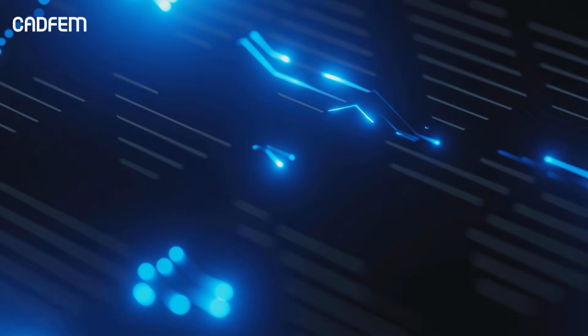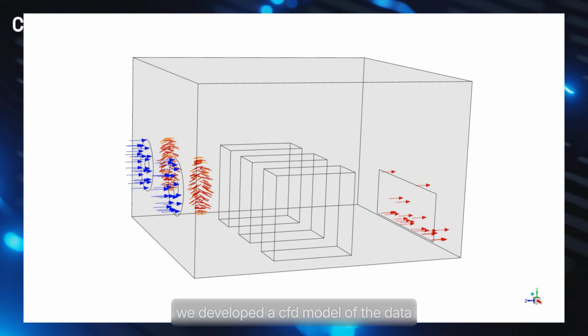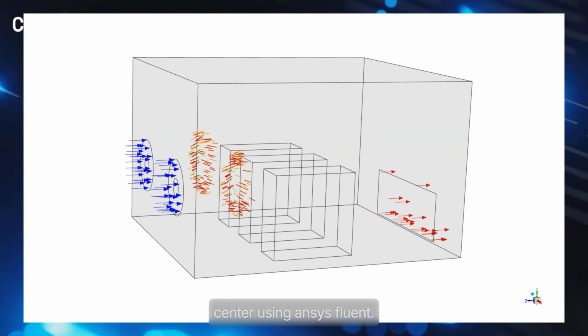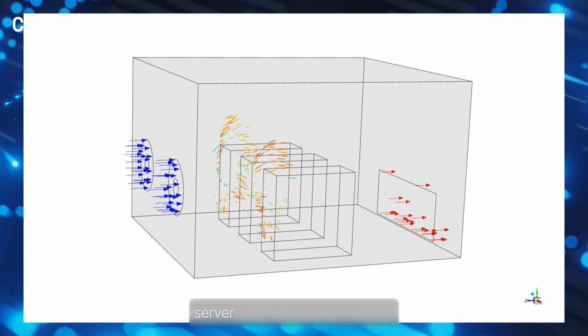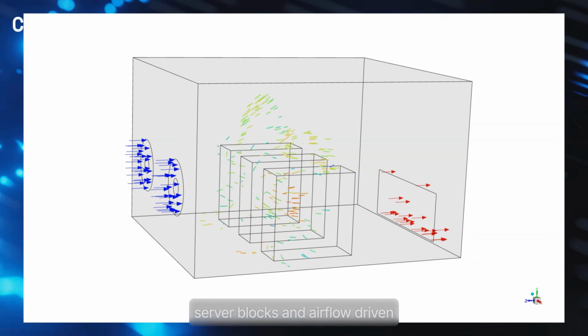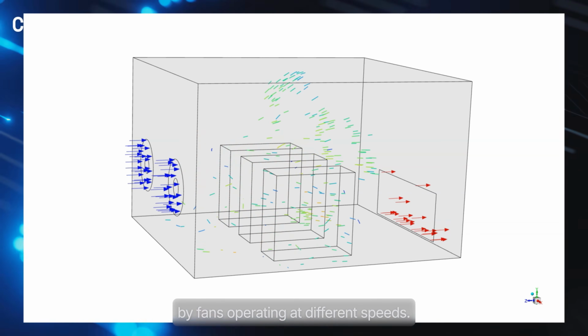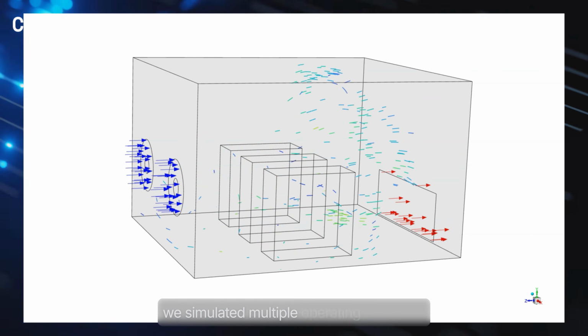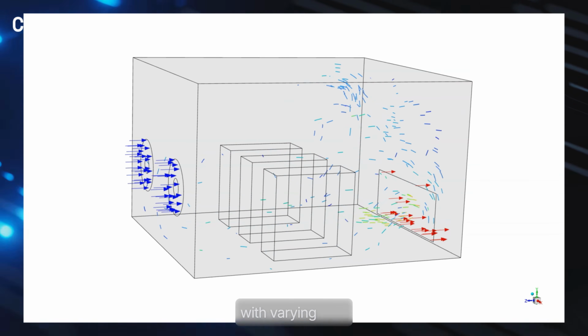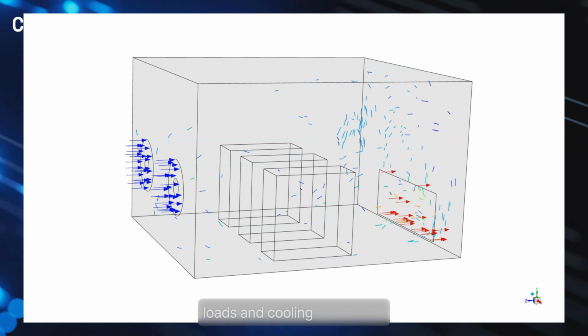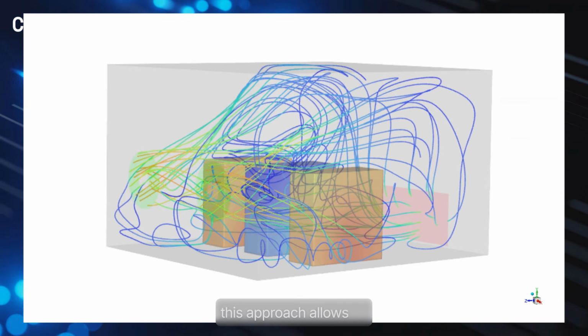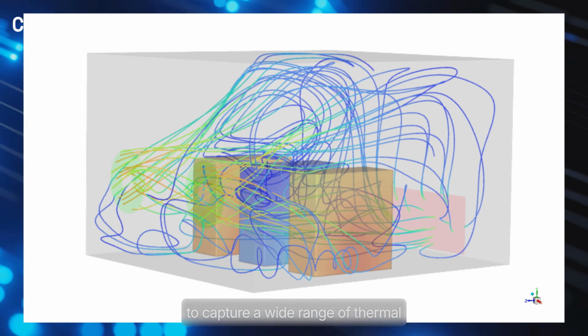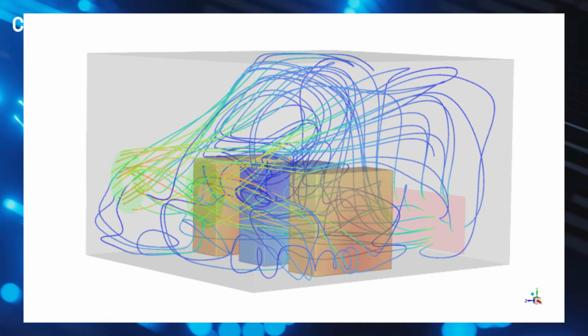To build this system, we developed a CFD model of the data center using Ansys Fluent. The model includes heat-generating server blocks and airflow driven by fans operating at different speeds. We simulated multiple operating scenarios with varying heat loads and cooling conditions. This approach allows us to capture a wide range of thermal behaviors within the system.